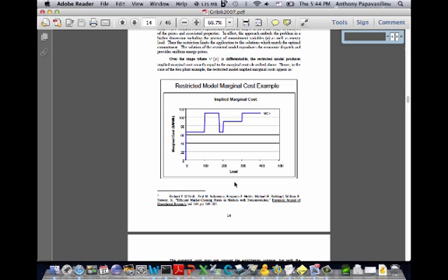It's a weird combined cycle unit like the model we're going to see now, where as you increase the loading, the marginal cost is definitely not increasing, so the cost is not convex. That's another source of non-convexity, another source of uplift payments. This is not a startup cost, but it's the same nature of the problem. It's a non-convex fuel cost.